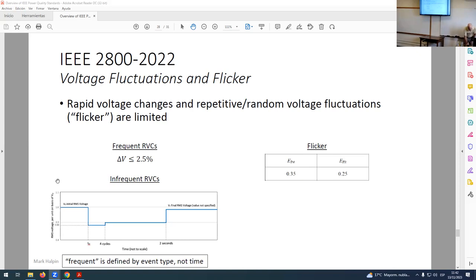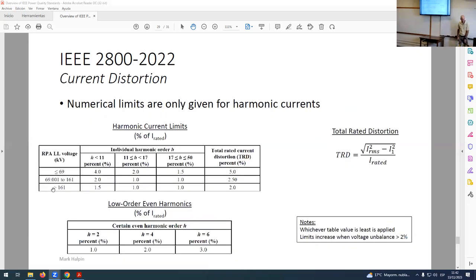As far as the harmonics are concerned, now, in this case, because 2800 deals with the whole range of potential transmission interconnection voltages, right? We have 3 rows, right? For lower voltages in the transmission range, for the intermediate voltages in the transmission range, and for the higher voltages in the transmission range. As you might guess, the higher the interconnection voltage, the more restrictive the limits.